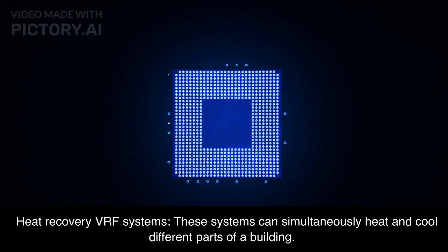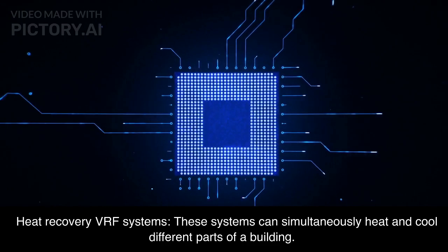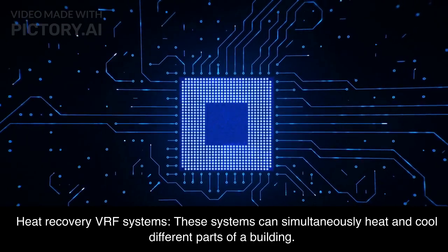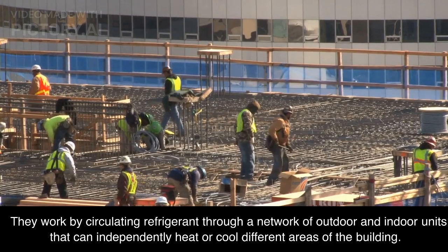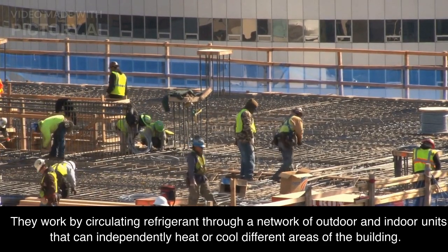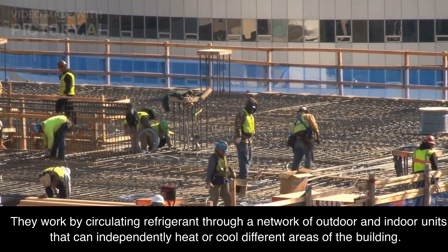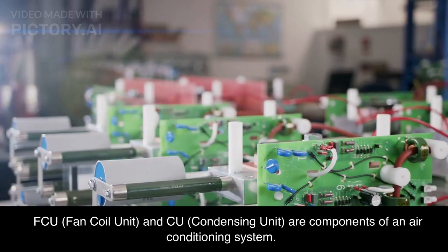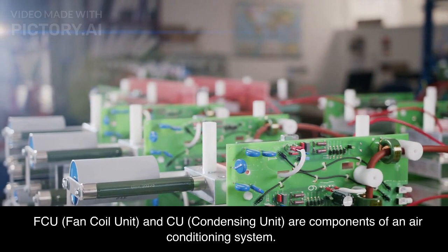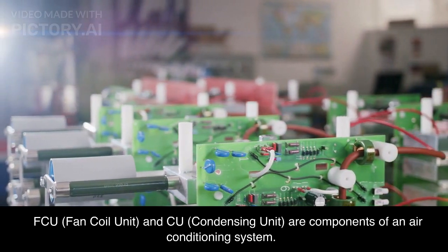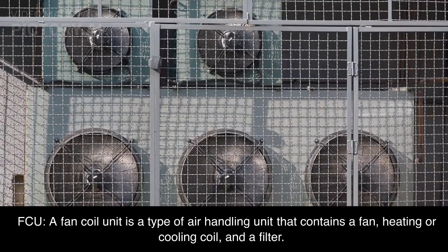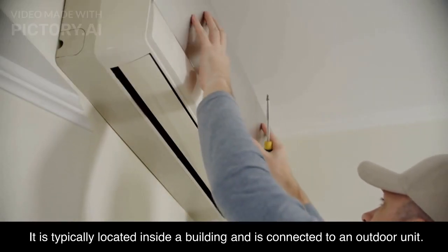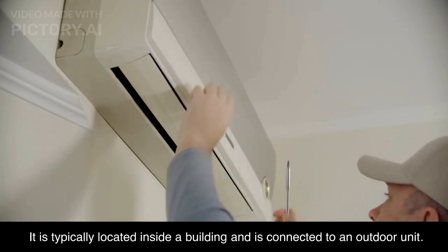Heat recovery VRF systems. These systems can simultaneously heat and cool different parts of a building. They work by circulating refrigerant through a network of outdoor and indoor units that can independently heat or cool different areas of the building. FCU, fan coil unit, and CU, condensing unit, are components of an air conditioning system. FCU, a fan coil unit, is a type of air handling unit that contains a fan, heating or cooling coil, and a filter. It is typically located inside a building and is connected to an outdoor unit.